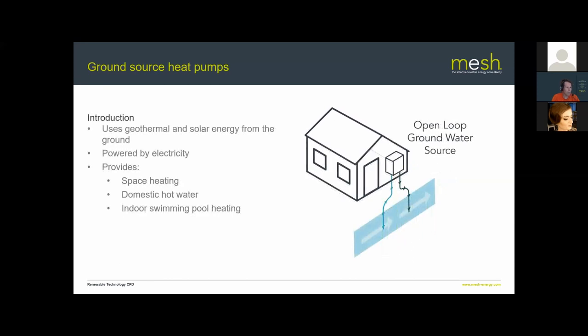Open loop ground source heat pumps extract groundwater, pass it through the heat pump, and return slightly cooler water to the ground. Across all ground source types, COP ranges from about 3 to 5, depending on heat pump design and the desired water temperature. The lower the flow temperature you require in the building, the higher the efficiency, because the heat pump has to do less work to amplify low-grade heat into high-grade heat.